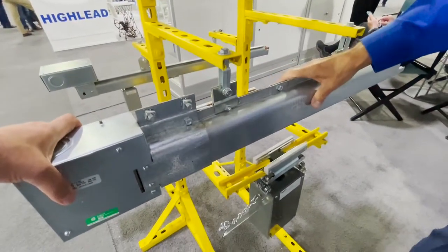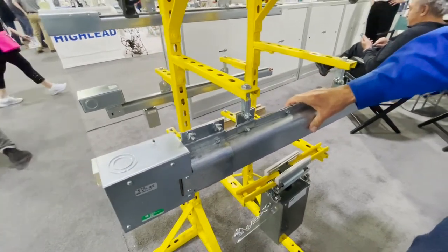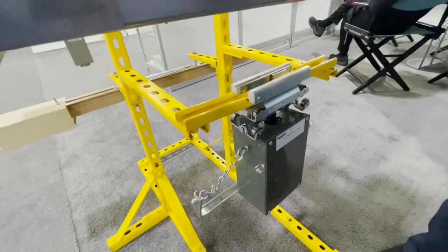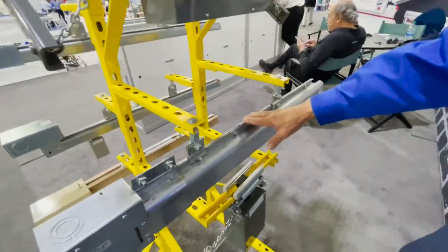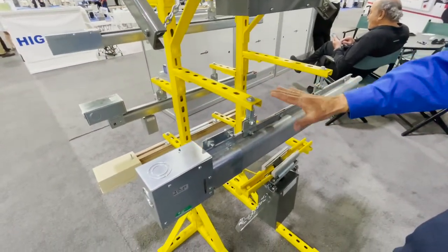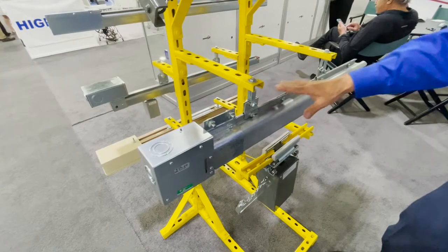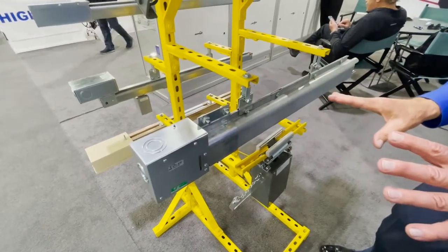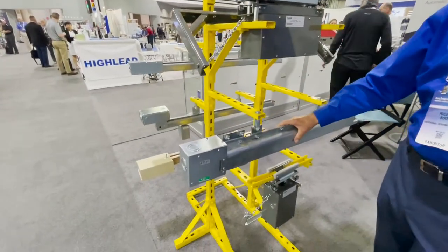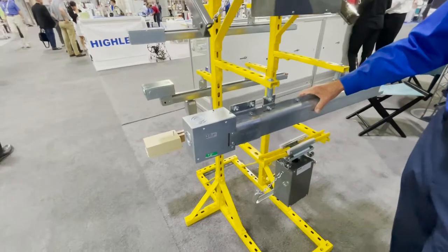This is the FR 100 system, rated at a continuous 100 amps. This is the trolley that goes into this system. The difference between this and the FH 22500 is that the FR 100 has trolleys available in 30, 60, and 100 amps. Both the FR 100 and the FH 22500 are trolley-only systems — no fixed plugs. They come in 10-foot sections.